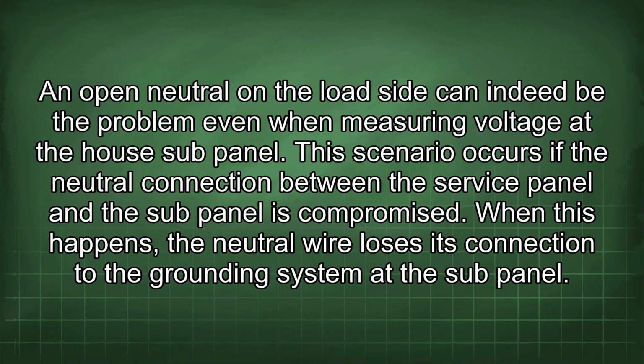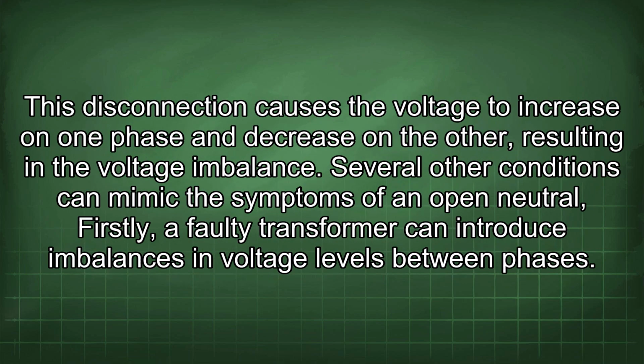An open neutral on the load side can indeed be the problem even when measuring voltage at the house sub-panel. This scenario occurs if the neutral connection between the service panel and the sub-panel is compromised. When this happens, the neutral wire loses its connection to the grounding system at the sub-panel. This disconnection causes the voltage to increase on one phase and decrease on the other, resulting in a voltage imbalance.